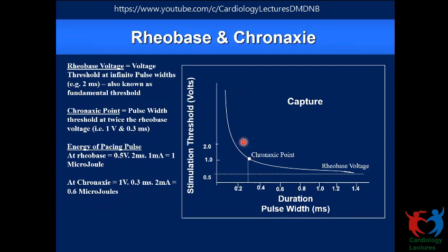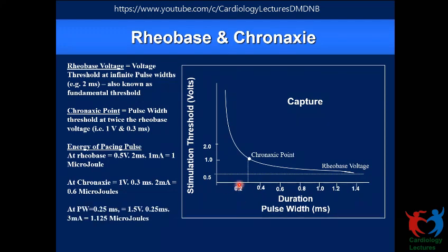So that's the importance of this chronaxis point, and this can be a reference point based on which I can program a two-fold amplitude to get a two-fold safety margin, or we can program a three-fold increase in the pulse width, which is 1 volt at about, in this case, 0.3. We can increase the pulse width to about 0.8 milliseconds. So either of these is okay, and will give a two-fold safety margin. But if we increase the pulse width beyond this point, then we are reaching the flat portion of the rheobase curve, or flat portion of the strength duration curve, and it is not going to be more efficient. It's going to increase energy delivery, but our threshold will not come down. And so also is the case if we take a significantly low pulse width, like in this case 0.25 millisecond, and then the voltage threshold might work out to about 1.5 volts, and the energy goes still more. The chronaxis point is the sweet spot.